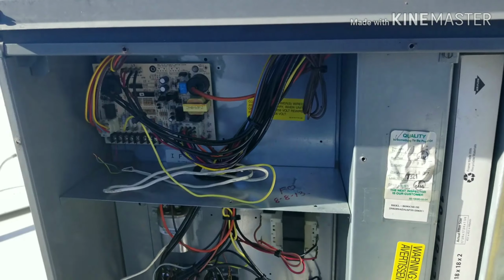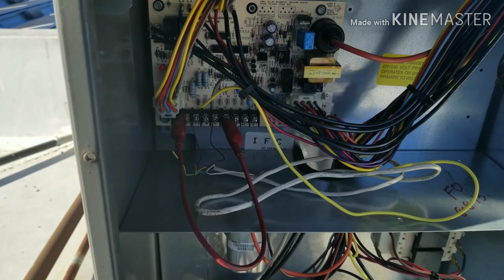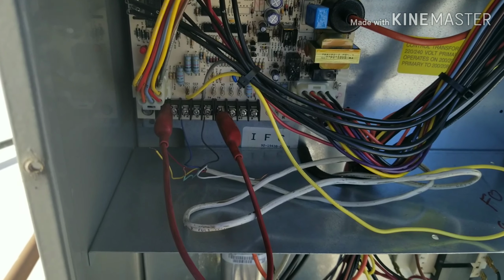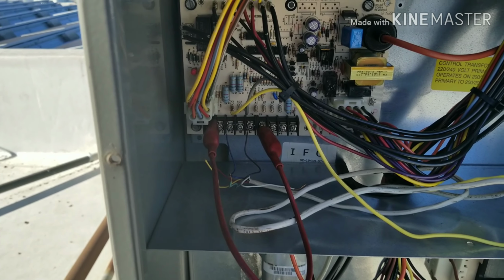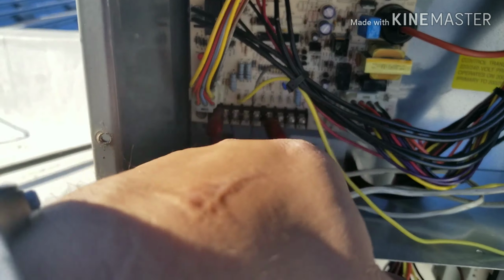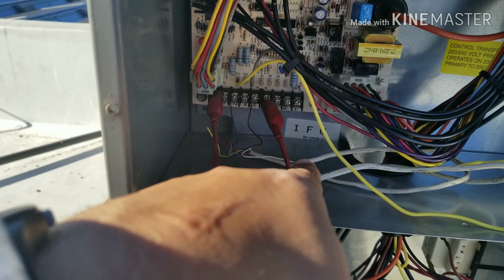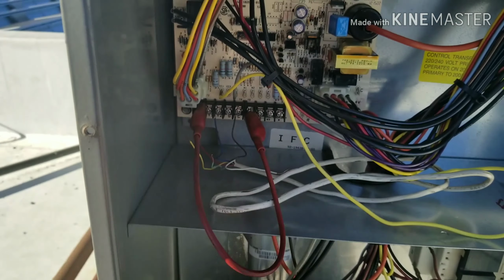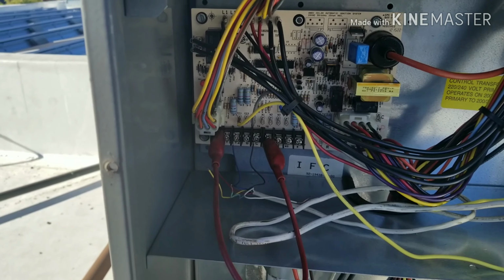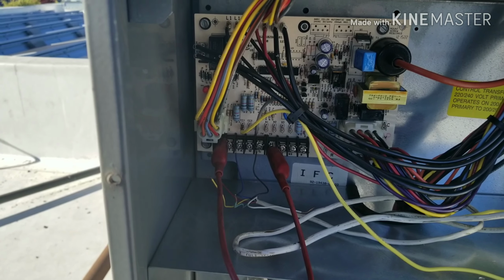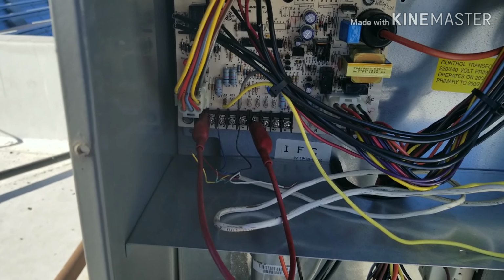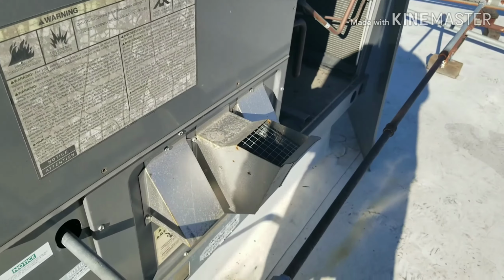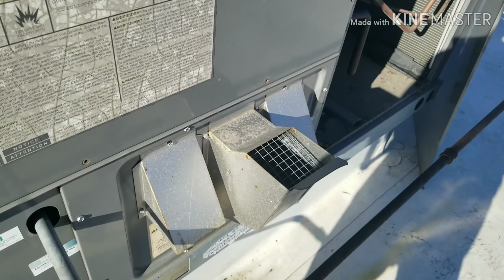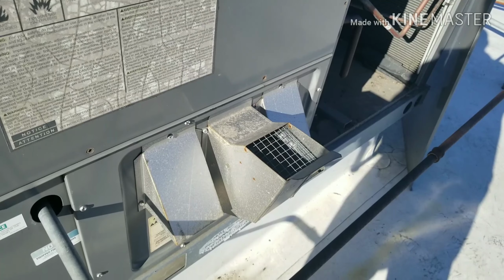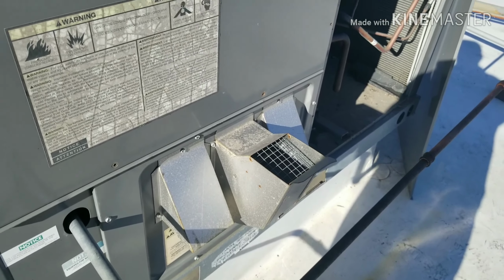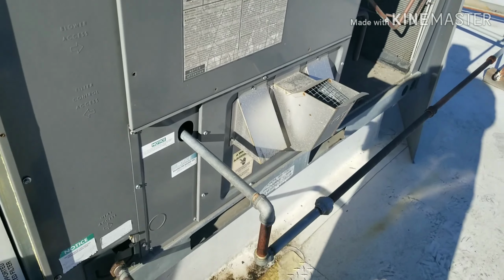We're gonna test the heating now. So I set the jumper for heating mode, and exactly what I told you guys not to do, that's what happened to me. This guy right here jumped off, and luckily it landed on top of the wires. So be careful. Make sure that you set it the right way. And now the inducer is running. It's purging the exchangers, inside the exchangers.